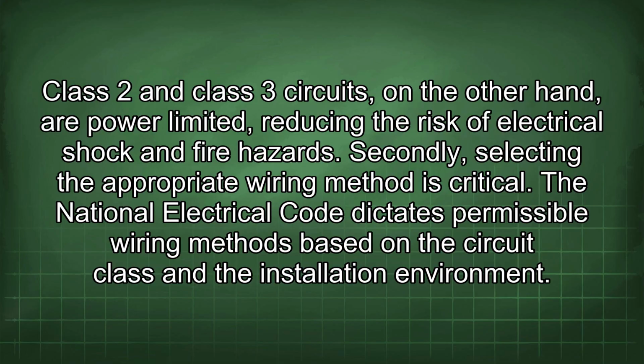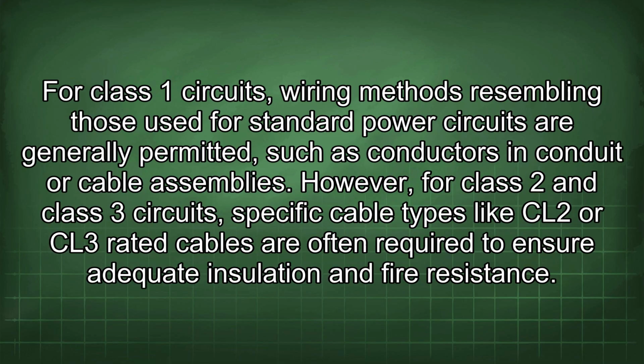The National Electrical Code dictates permissible wiring methods based on the circuit class and the installation environment. For Class 1 circuits, wiring methods resembling those used for standard power circuits are generally permitted, such as conductors in conduit or cable assemblies. However, for Class 2 and Class 3 circuits, specific cable types like CL2 or CL3 rated cables are often required to ensure adequate insulation and fire resistance.